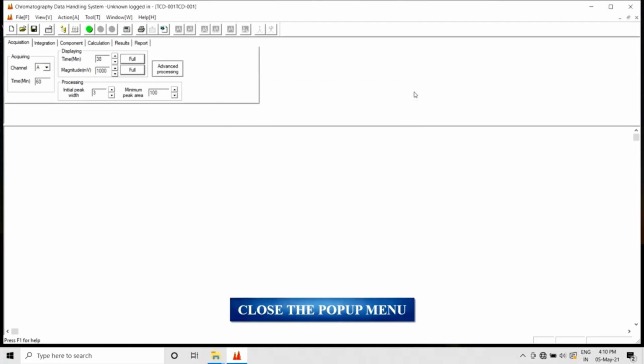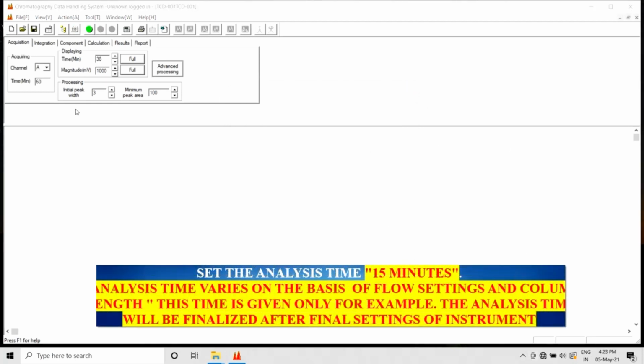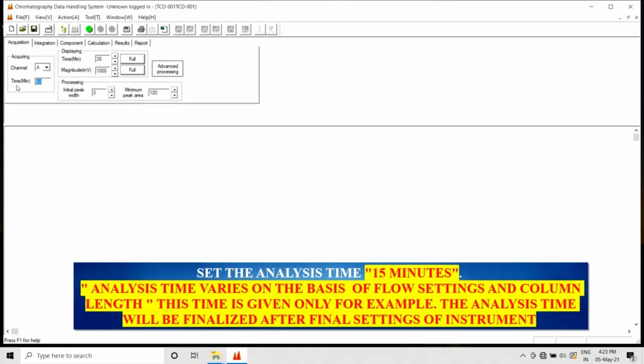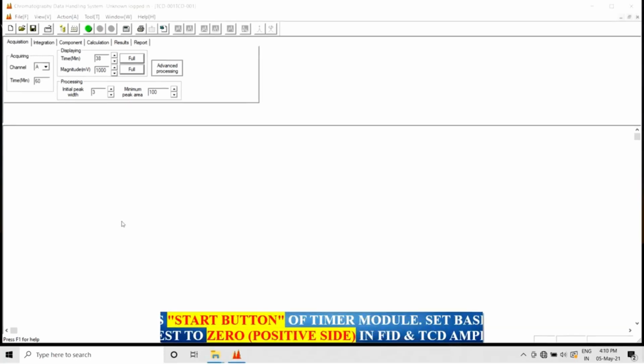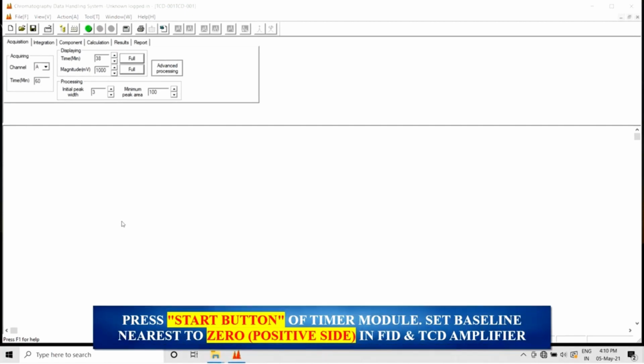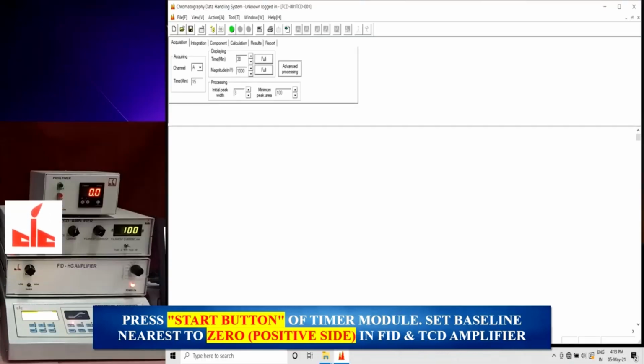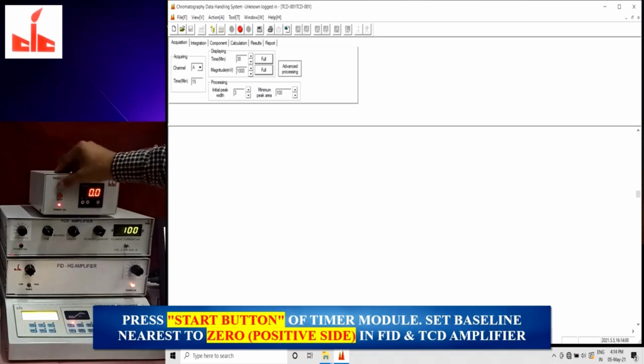Close the pop-up menu. Set the analysis time, 15 minutes. Analysis time varies on the basis of flow settings and column length. This time is given only for example. The analysis time will be finalized after final settings of the instrument. Press the Start button of the timer module. Set the baseline nearest to 0, positive side, in the FID and TCD amplifier. The analysis is started, and timing can be seen on the timer module.